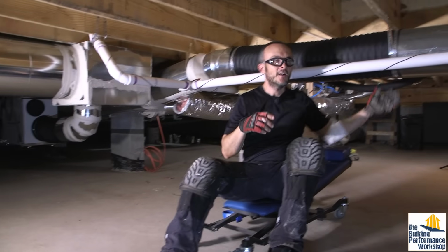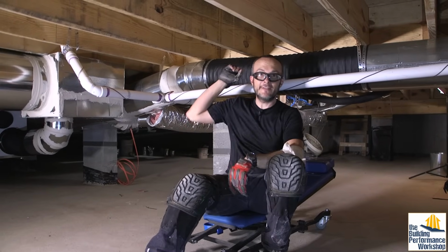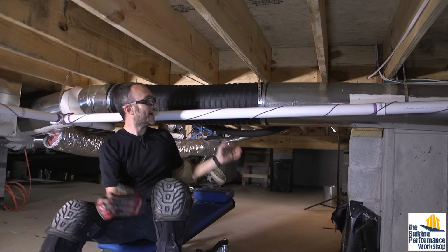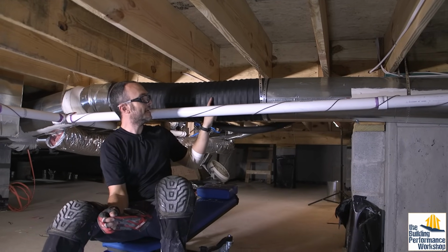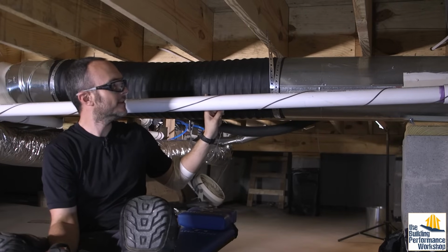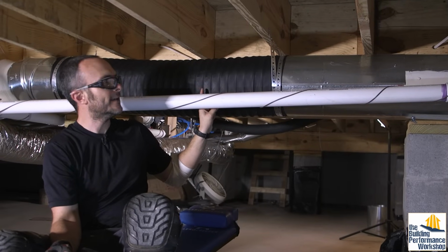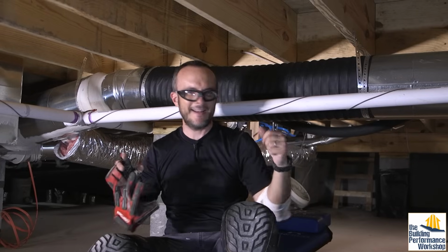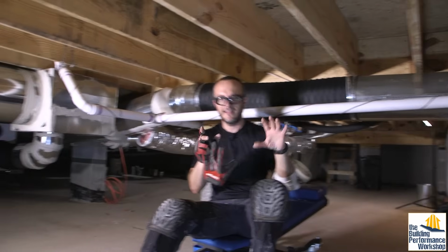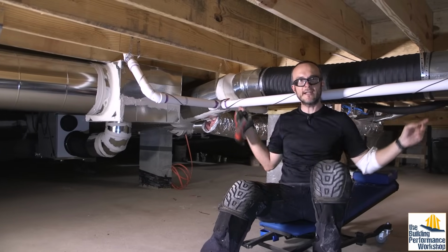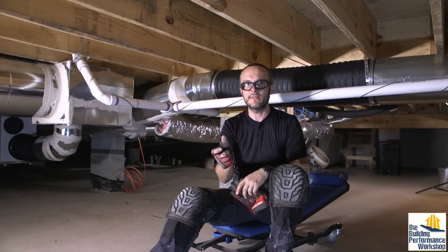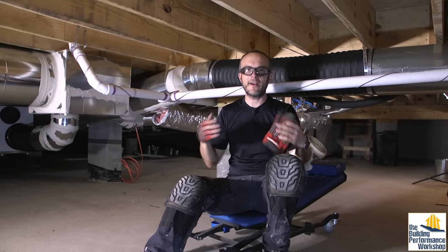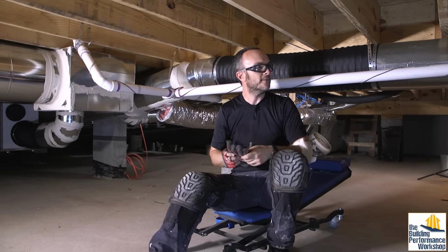So you can see here where we've got a really excellent use of flex duct in conjunction with rigid duct. This all will be insulated, and I will have to come along and inspect this, but this is not the same very flimsy plastic material. This is a more durable type of flex duct, and I needed to be able to connect these two things that are not really in line with each other. They're just a little bit off, and you would literally spend hours trying to figure out how to connect these two things if you were using a rigid material. So being able to use the flex duct in this case just saves a lot of time, and it doesn't matter that it's just a couple inches off or that it's at the wrong angle.